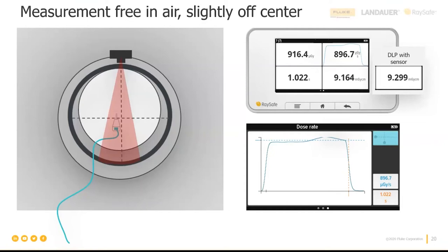Yeah. So we actually also have a question from the audience. So this measure has to be axial, right? Is the question. Right. So whenever you use a CTDI ion chamber, the scan has to be an axial scan. When you perform free in air or CTDI measurements with an ion chamber, the only option is axial scan. The values can later be recalculated for a helical scan. So you don't destroy your chances to measure just because you're using the axial scan.